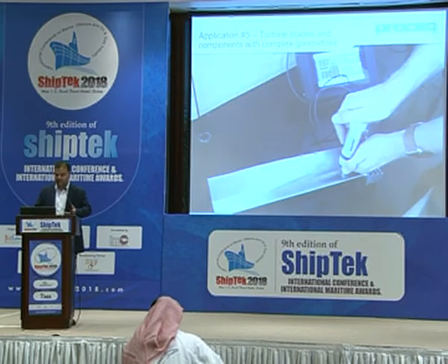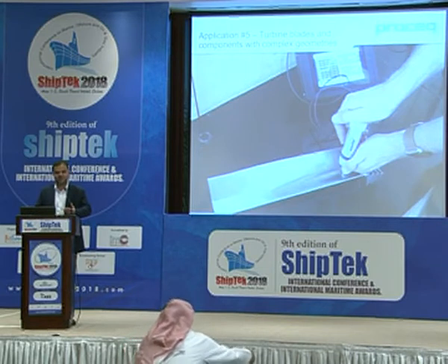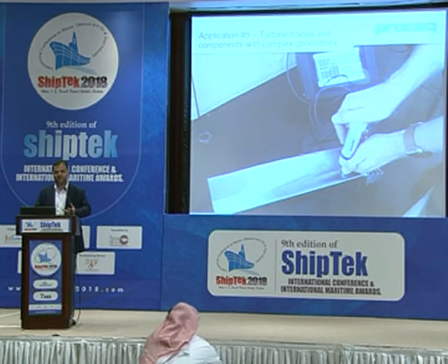Again, turbine blades and components with complex geometries, which has been always a challenge. So with the UCI, with the precise positioning and the lower thickness up to 5 millimeter, we can easily address this application as well.